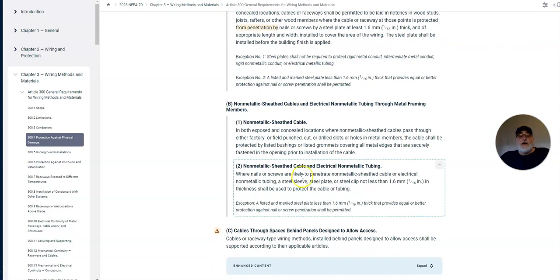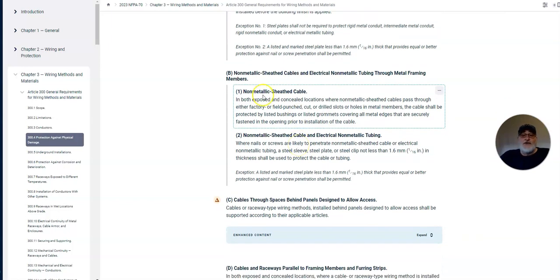Okay. Non-metallic sheath cables, electrical non-metallic tubing through metal framing. So now we're talking about commercial. Nine times out of 10, boys and girls, we don't use non-metallic sheath cable in commercial buildings unless you're using it for temporary lighting, and that's kind of frowned upon nowadays too. Electrical non-metallic tubing, they're going to talk about that here in a minute. That's what we call Smurf tube in the trade. It's flexible, looks like conduit, it's round, and it's got ridges inside of it. A lot of electricians don't really like it because it's harder to pull wire through.